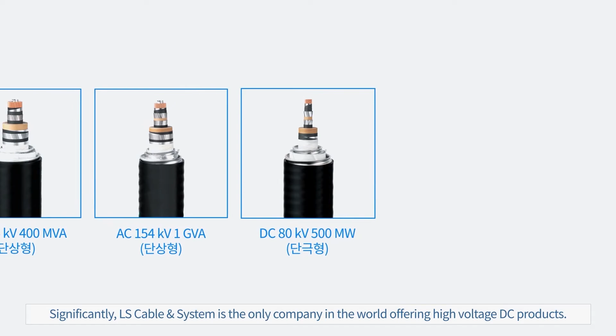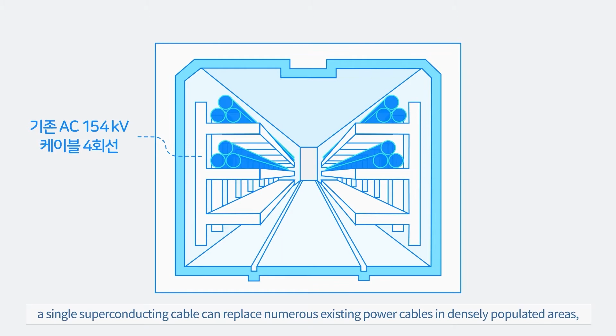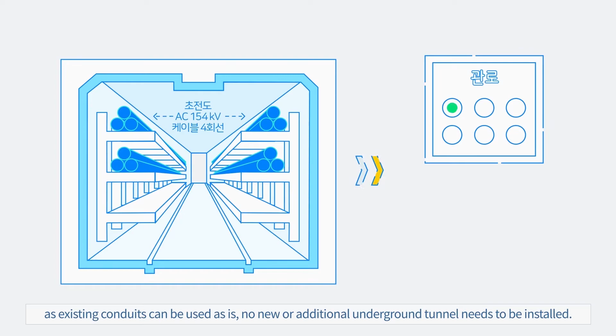As the superconducting cable system enables bulk power transmission at low voltage with high efficiency, a single superconducting cable can replace numerous existing power cables in densely populated areas, since existing conduit can be used as is. No new or additional underground tunnel needs to be installed.